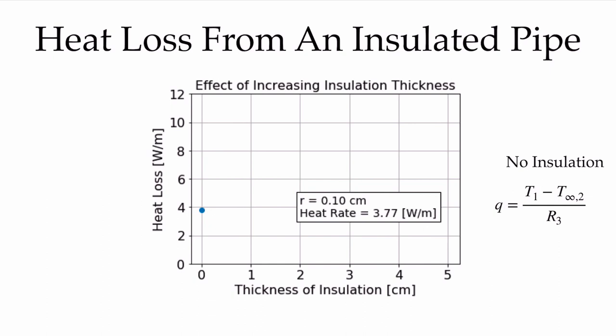I have this high-temperature fluid in the pipe and it's cold outside, so I should insulate it to save money. Let's start by adding a small bit of insulation and see what happens. We've added the insulation, so we have both the conduction resistance through the insulation and the convection resistance. The white part is the pipe itself and the black ring represents the current thickness of insulation. But notice what's happened — my heat rate has gone up from under 4 up to 6.62 watts per meter. We've added insulation and the situation has gotten worse; we're losing more heat.